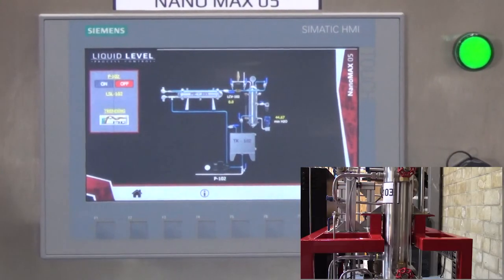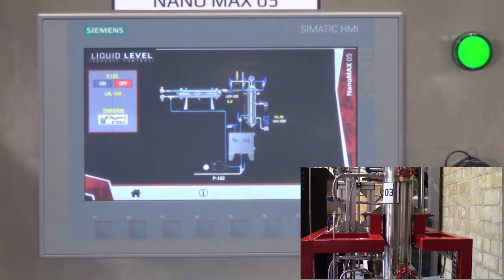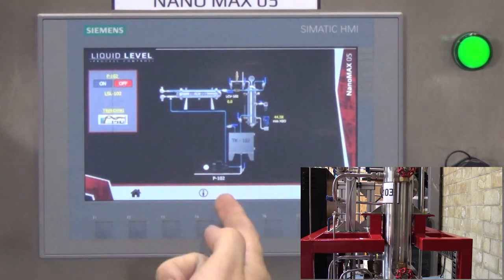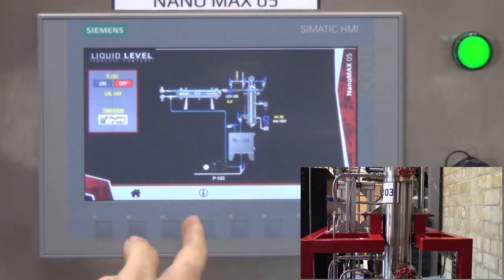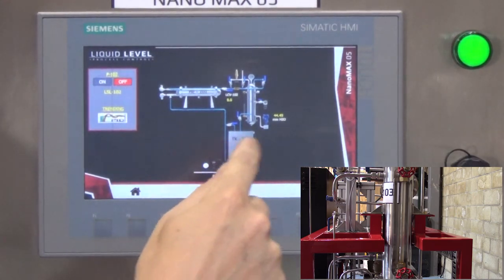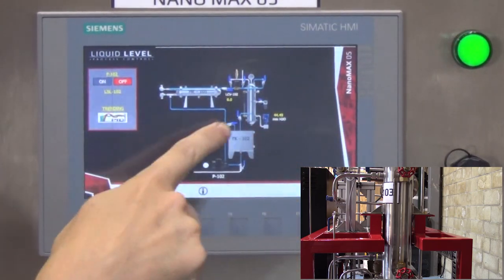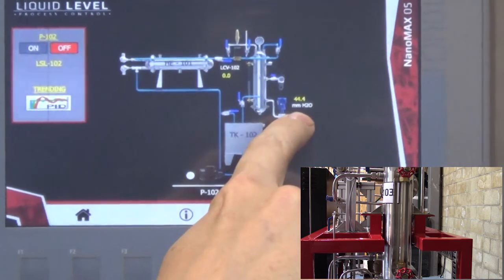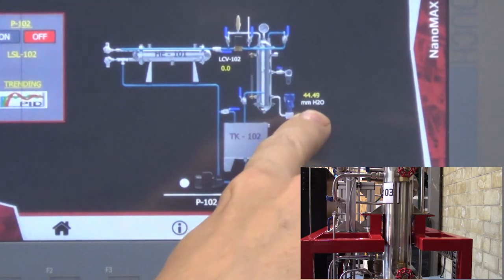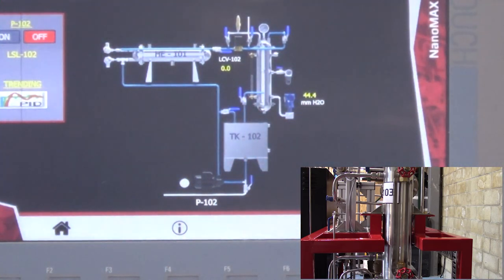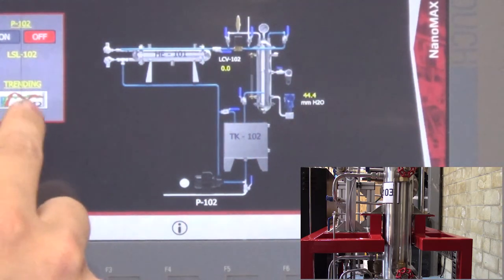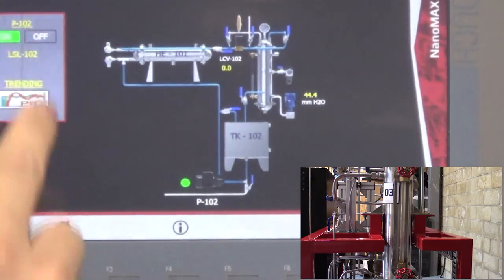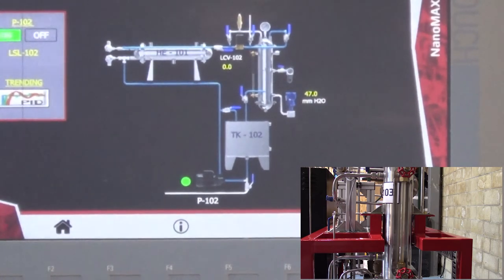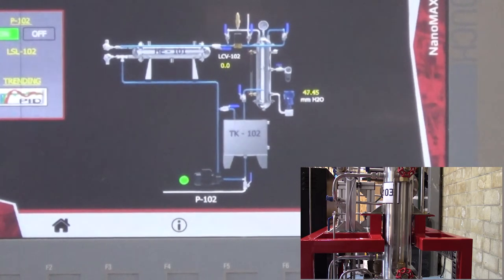So we'll fire that up. Again, using our touchscreen interface, we have a view of all that is involved in the process. And our focus here is this tank right here and our level in millimeters of H2O for pressure differential inside of the liquid level tank. So I'm going to touch the touchscreen, and this turns on the pump. You can hear the pump running in the background.